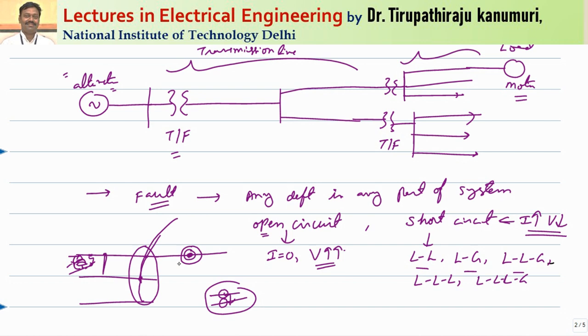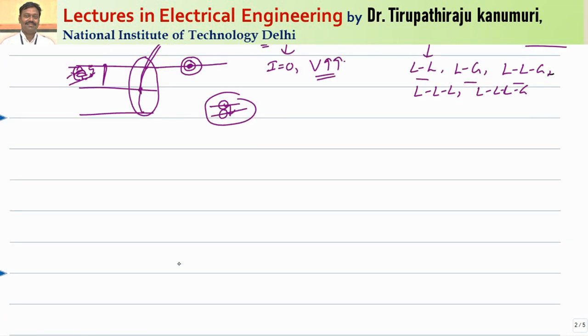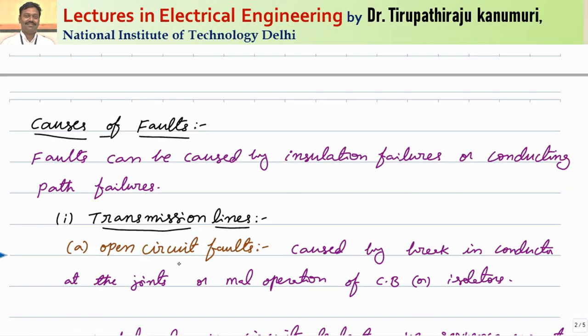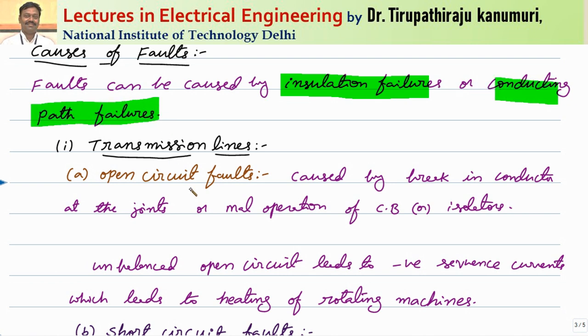That is why generally re-closure of the circuit breaker is done to check whether the fault is permanent or temporary. This type of thing is not done in the case of cables or alternators. So the faults can be caused either by insulation failure or conducting path failure. Conducting path failure means the conductor is broken; insulation failure means the conductor is touching ground or another phase.